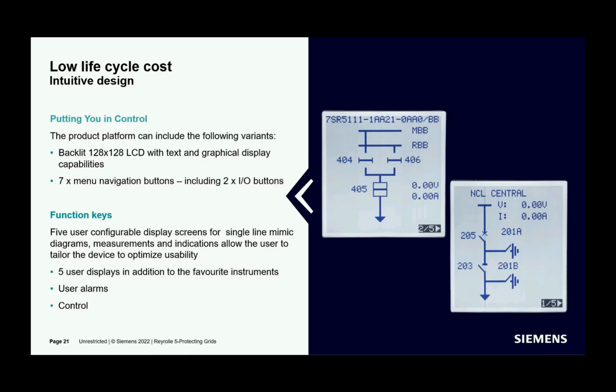There is also a feature called favorite instruments, which is also described by a video outside this presentation, and this allows the user to choose the most necessary measurements out of all available predefined measurement displays. So there are already many measurements, and you can choose any favorite one, and you can set it on a hot button inside the first menu item inside the fascia, and you can access it fast. And of course, the single line diagram allows the user to control the switching device via navigation buttons and the 2 circuit breaker control buttons provided.